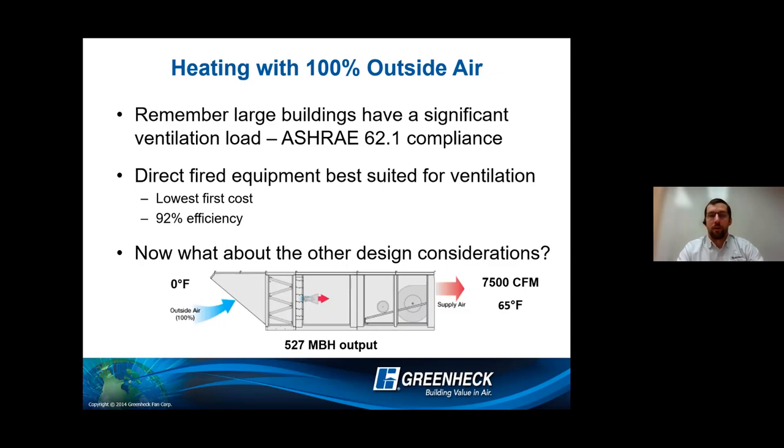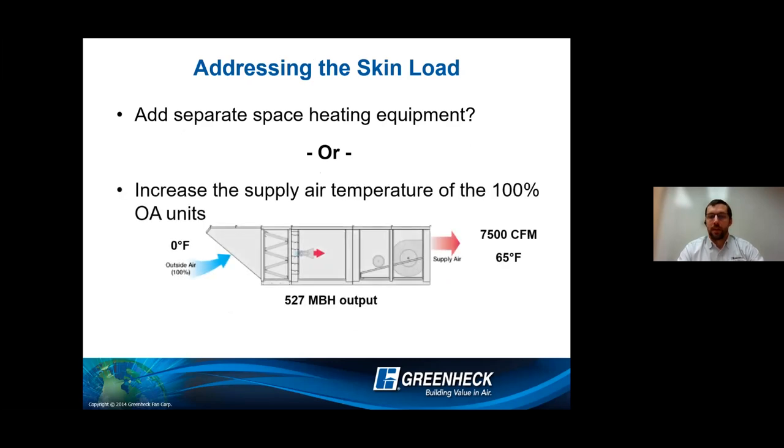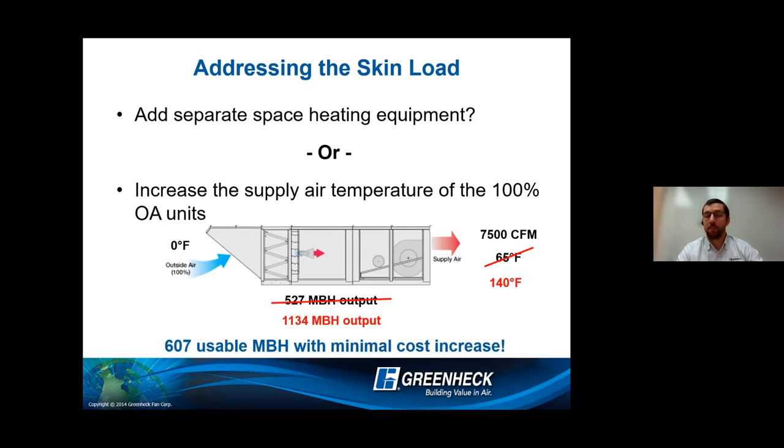Now, we've got that situation. What about our skin load in that space? Well, we can either add separate space heating equipment, so we can add some infrared tube heaters or, say, unit heaters within the space. Or we can simply increase the supply temperature of that 100% outside air unit. So instead of discharging 65 degrees, let's crank that up to about 140 degree discharge.